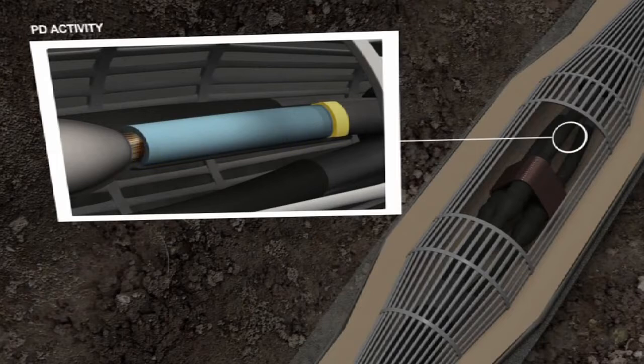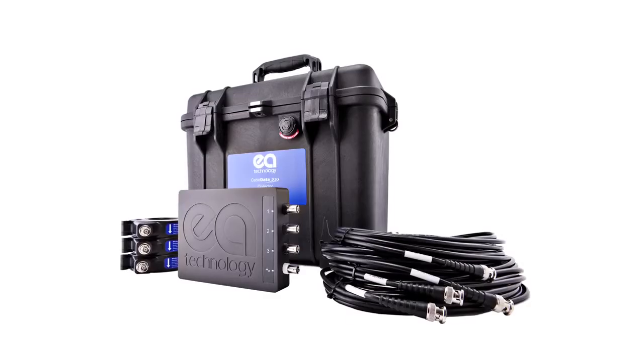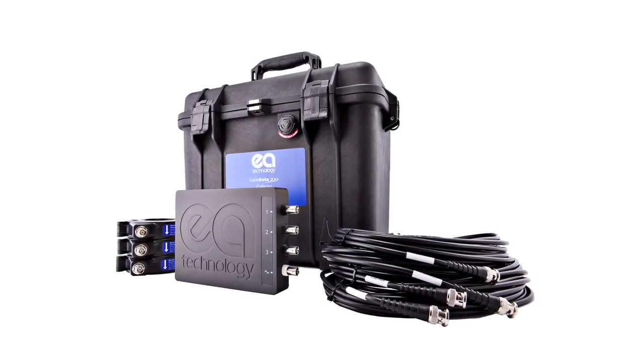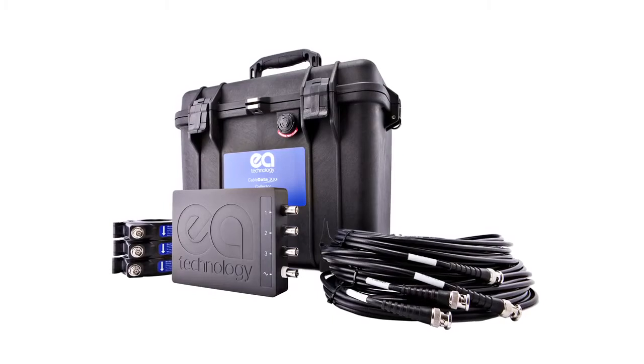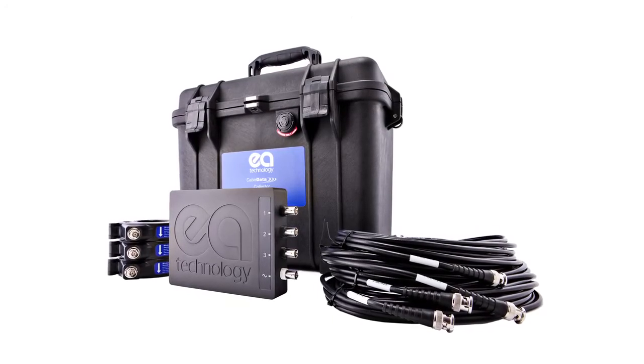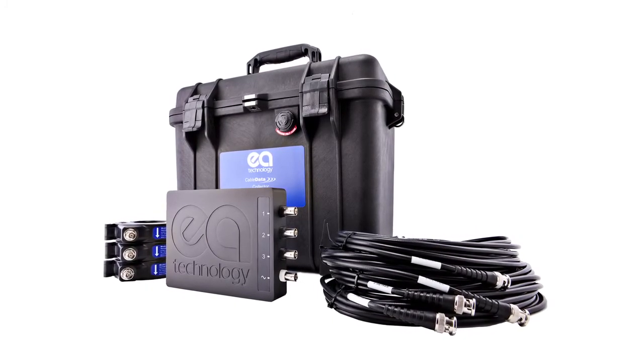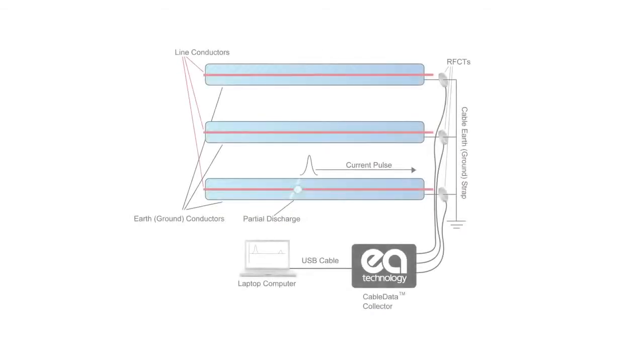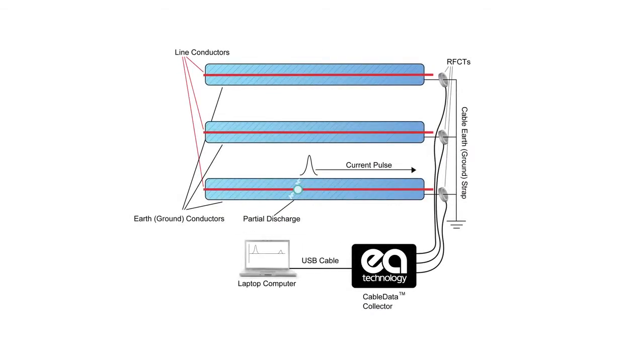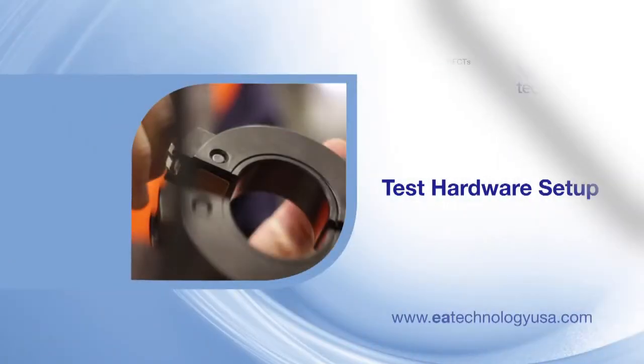So, we need a reliable way to test for PD in live cables, without the need to take them offline. The Cable Data Collector is a complete solution to the problem of testing for PD activity in all commonly used distribution voltage cables, single phase or three-phase. It works by measuring radio frequency currents, which are produced when discharges occur. Simple, effective, and no need for a planned outage. So, let's take a look at how to perform a test and what to do with the information it produces.